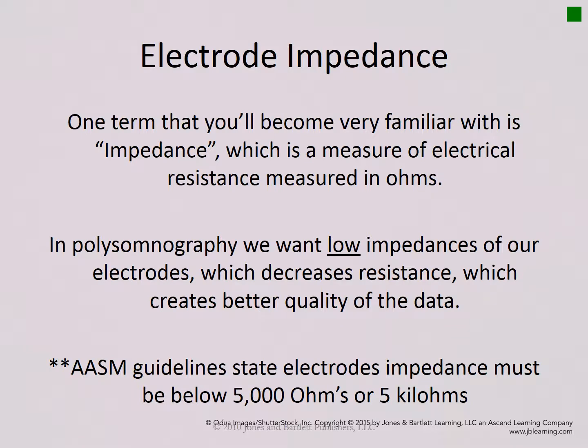Electrode impedance. One term that you'll become familiar with is impedance, and this is a measure of electrical resistance measured in ohms. And we talked a little bit about this last week. Remember, we want to have low resistance so we can more efficiently collect the current and measure the voltage. So we want to keep our ohms low. In polysomnography, we want low impedances of our electrodes. This decreases the resistance and it creates better quality of the data. AASM guidelines state electrode impedance must be below 5,000 ohms, which is the same as 5 kilo ohms.